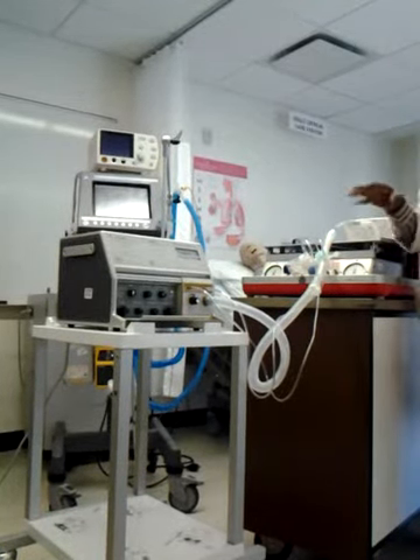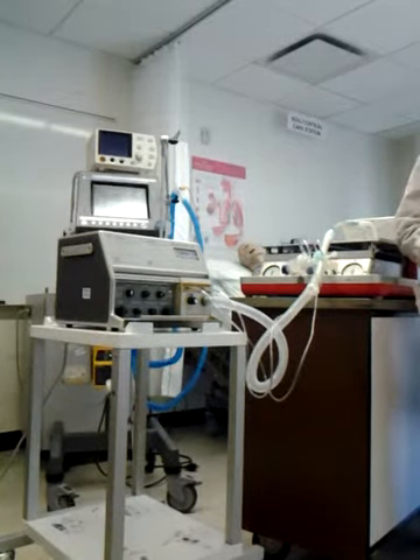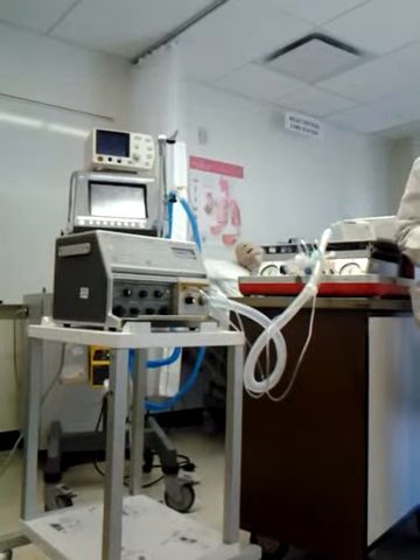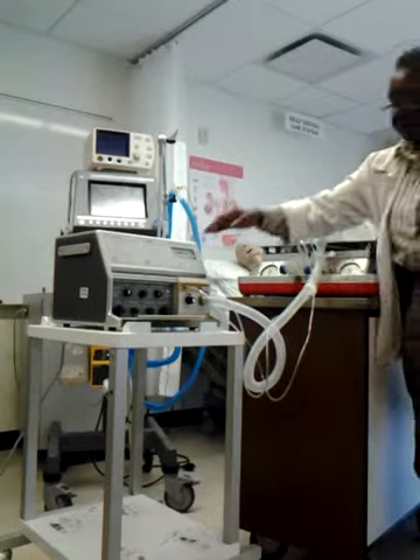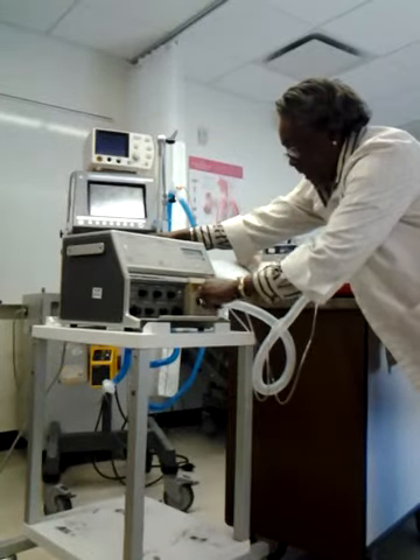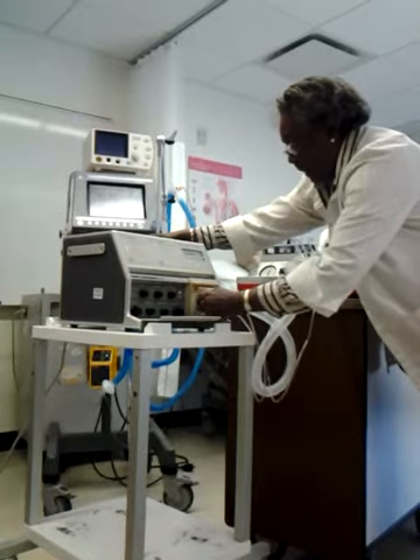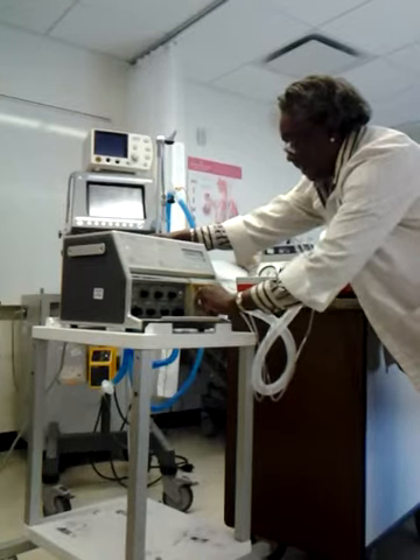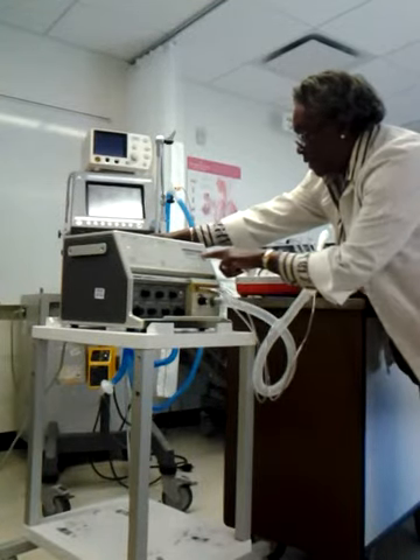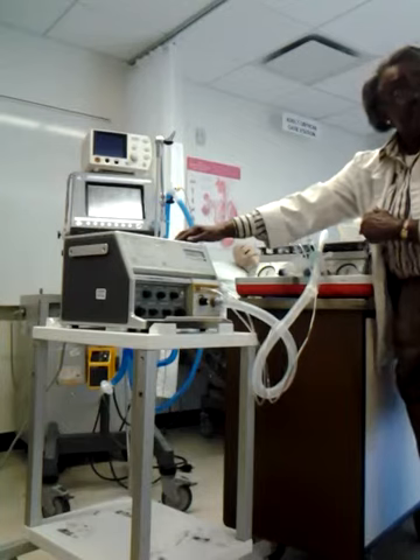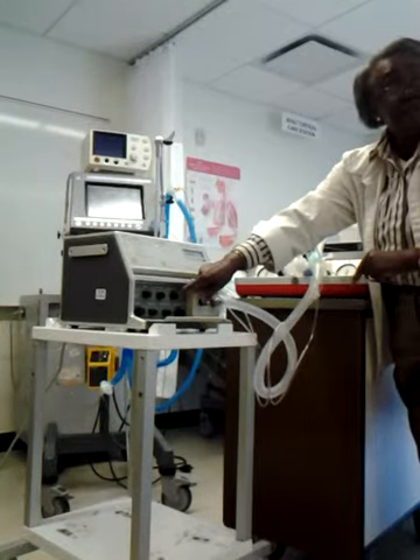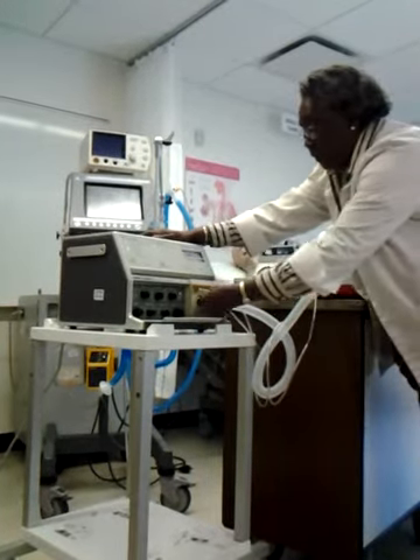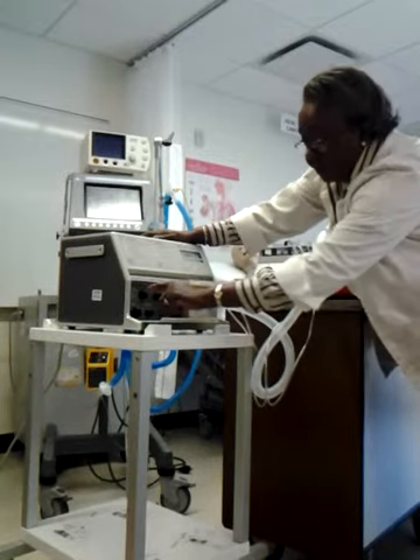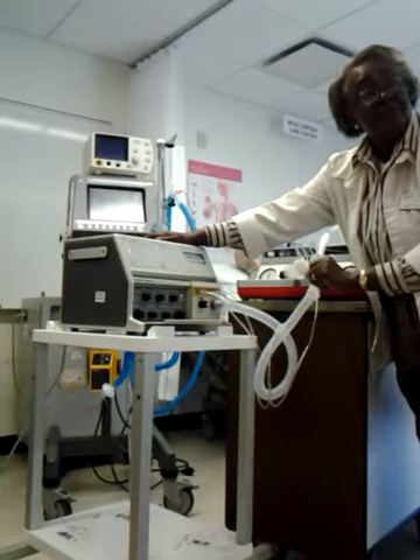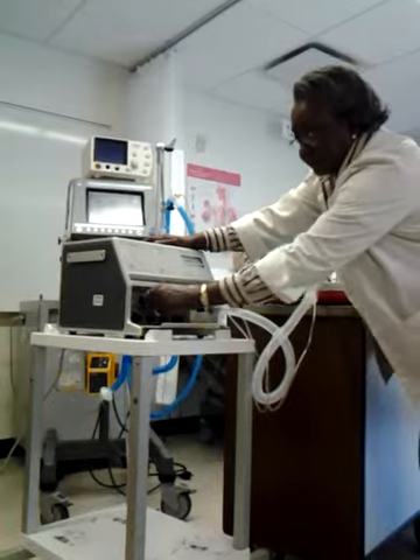It's usually volume ventilation. But they did include that because on those rare occasions, it may happen. So you would unhook it from the patient, occlude it, and then push this knob in and turn it. Which does what? Gives it a breath? No, it just actually allows you to set peak pressure, so for pressure ventilation. Here you're not setting a pressure limit for volume ventilation. By using this button, you're in pressure control, and that sets your pressure for pressure ventilation.